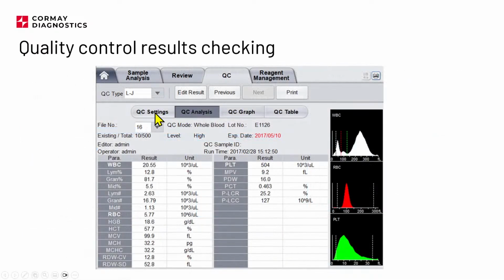And when we set up the QC, what you need to do is set up the QC for each level, right? So let's say that in the previous step we only set up the QC for the low level. You also need to set up the normal, the high level, and also need to set up the CRP, right? So keep in mind that you need to make a few files. And when you have set up everything, then you can go to the QC analysis, and this is actually the menu which allows you to run QC analysis. From the file number, you just need to choose which file you want to use. And let's say that this is your first installation. So you will have 3 levels for hematology and 3 levels for CRP reagents or CRP modules. So you will have 6 files, not 16 like in this case.